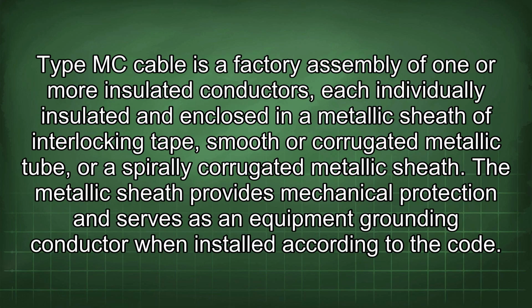Type MC cable is a factory assembly of one or more insulated conductors, each individually insulated and enclosed in a metallic sheath of interlocking tape, smooth or corrugated metallic tube, or a spirally corrugated metallic sheath. The metallic sheath provides mechanical protection and serves as an equipment grounding conductor when installed according to the code.